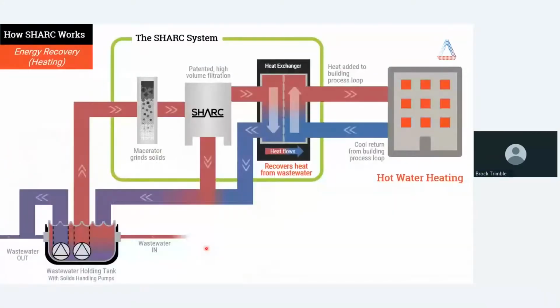And in terms of an installation, two quick slides just to illustrate how energy is moved through the system. Both the exact same installation, we're just moving energy in two different ways. So first, what we're going to look at is energy recovery. In this case, you're going to see the same type of wastewater holding tank or collection point. All of that sanitary wastewater is going to be used. We pump the wastewater up and through the Shark system. And first, we have what we call a macerator. Any of the larger diameter solids that are moved from your wastewater collection point will enter into this macerator. And this basically grinds down or chops down any of those larger solids into smaller, more manageable diameter pieces that will then enter into the Shark.